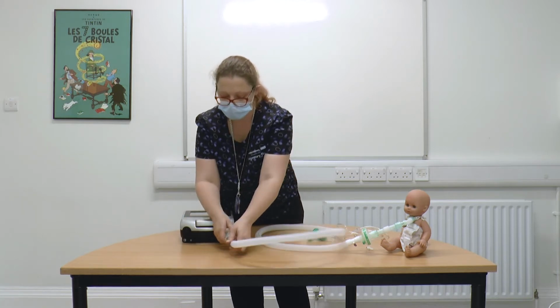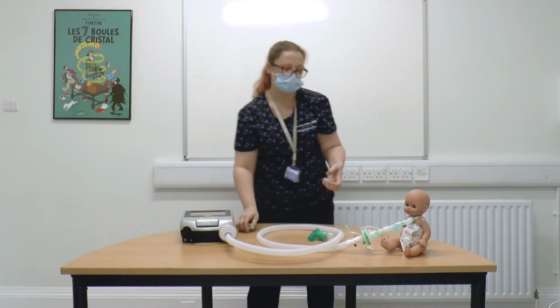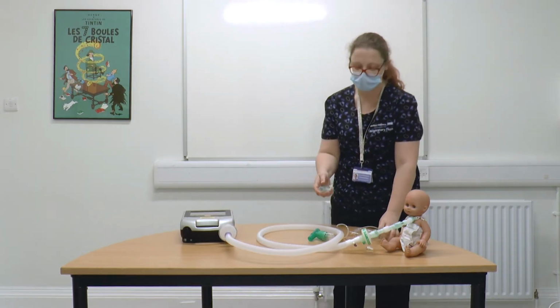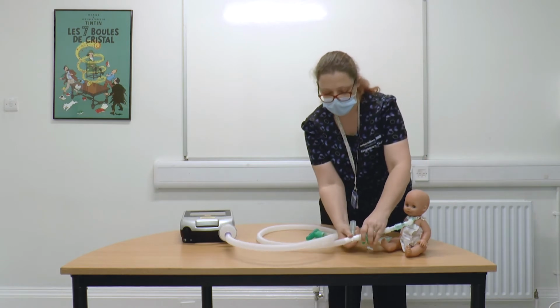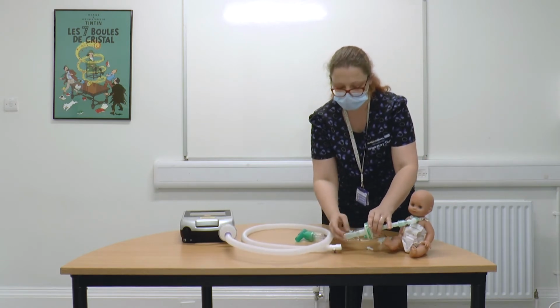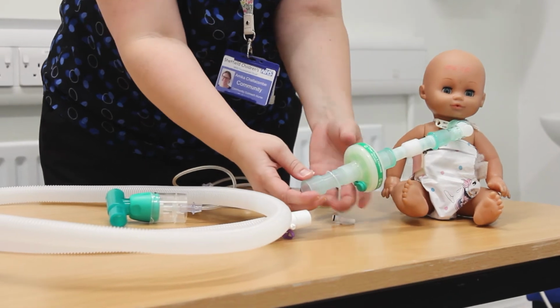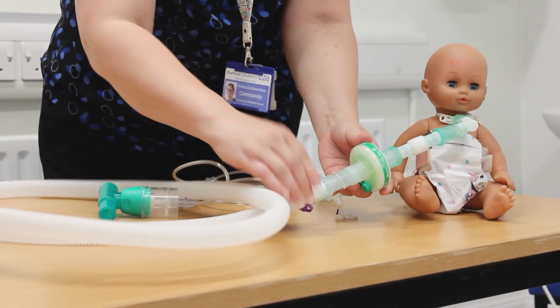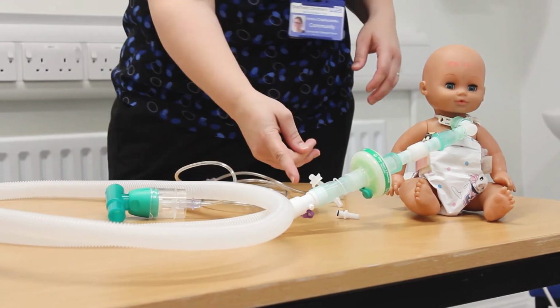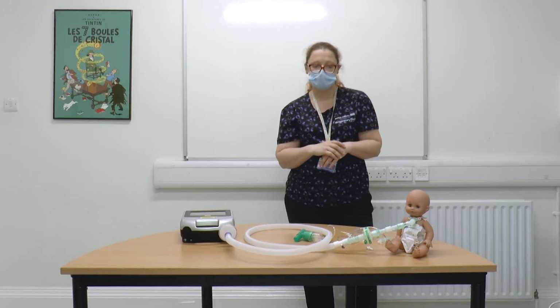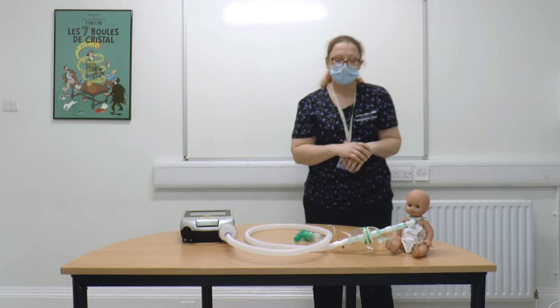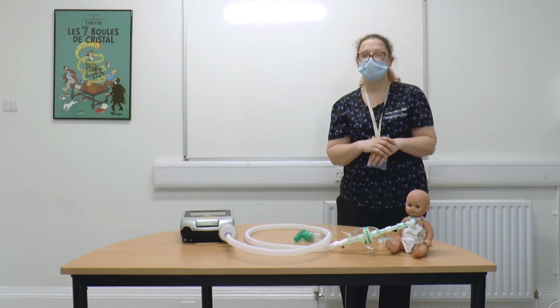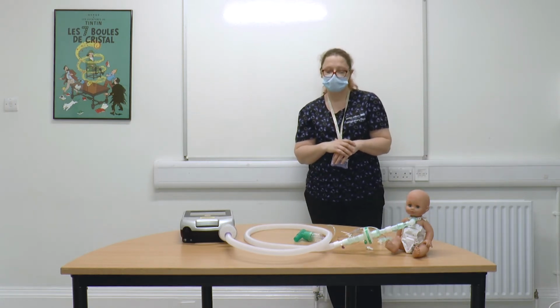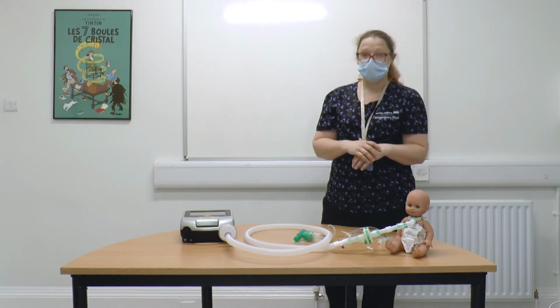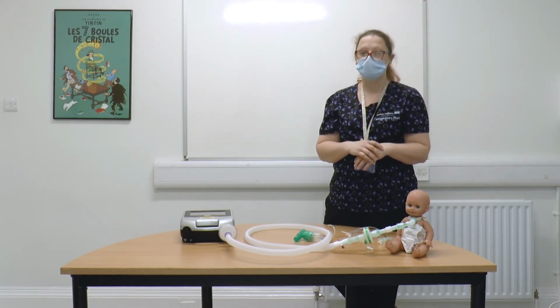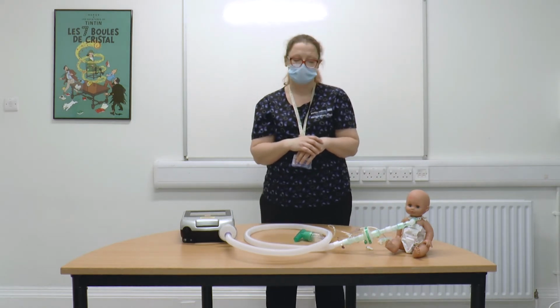Other children who don't require oxygen all the time but may just need a blast of intermittent oxygen, such as when they have some sort of seizure, may need to have the oxygen nearer to them. This is often attached to the HME in between the exhalation valve. Again, remove the cap if you want to put your oxygen tubing on. Ensure that if you remove the oxygen tubing, the cap is returned. You should not be using more than 5 litres through the front of the ventilator circuit. That is the same for any type of ventilator, because the flow will change the pressure the ventilator is delivering.